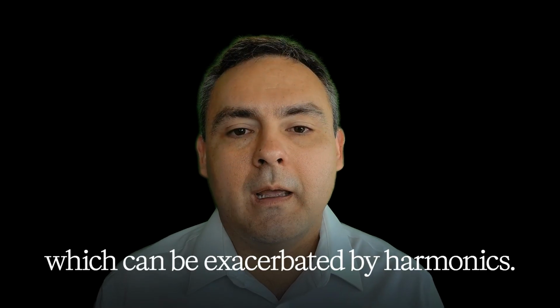And if we're already doing grid tie, solar, batteries, or large loads, our interconnection agreement may already require compliance. But what's far more common is this: power factor penalties, which can be exacerbated by harmonics. If our site's power factor drops below 0.9 or 0.95, our utility may apply penalty charges, demand ratchet increases, or reclassification into a higher billing tier.